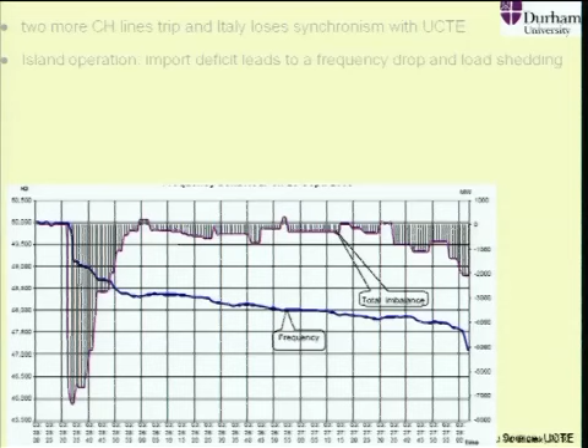As frequency was dropping very quickly, automatic load shedding was activated. As you can see, they also switched off the pumps—they had a lot of pumps, so they switched those off. So the deficit of generation was completely negated, and they even had a surplus of generation.